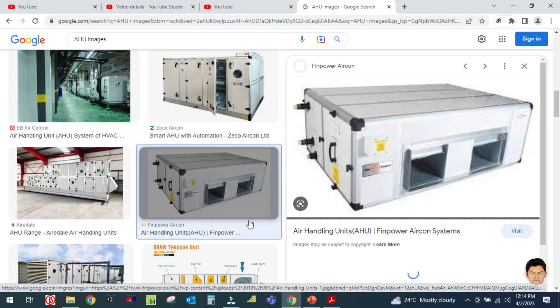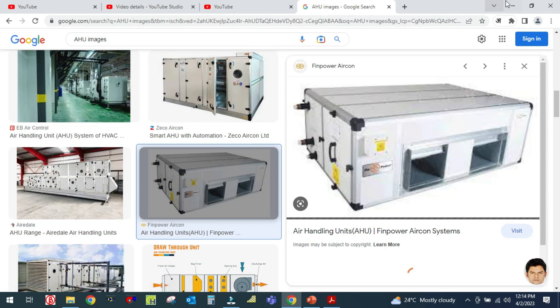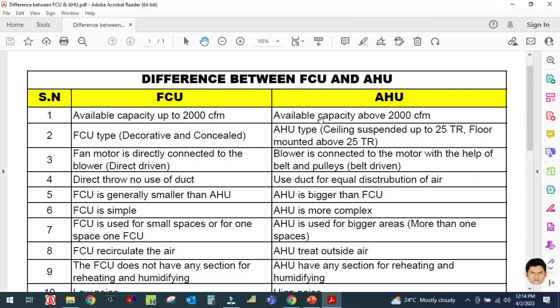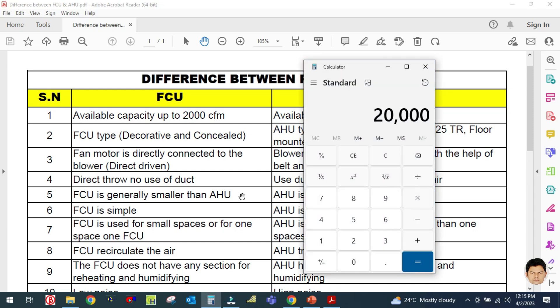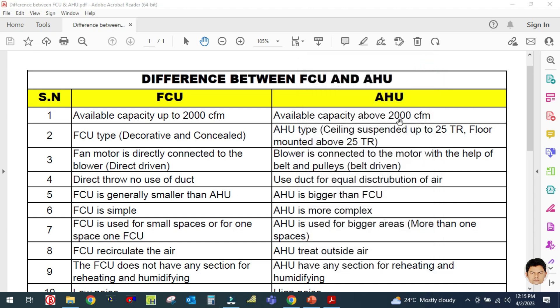This is the AHU — ceiling suspended type. The maximum available capacity of an air handling unit is 2000 to 20,000 CFM. So 20,000 CFM divided by 400 is approximately 50 ton. The second difference is that the fan coil unit is available in decorative and concealed types, while the air handling unit is ceiling suspended type and floor mounted type.